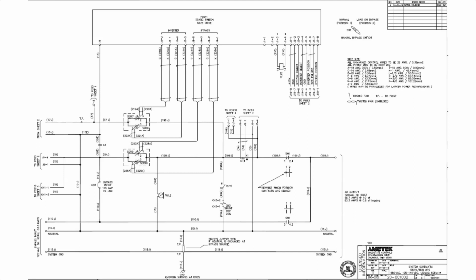So this is the same drawing that we had for the static switch. So you can see once again, here's our inverter static switch, and here's our bypass static switch. But you can see here we have switch 1, and we have two contacts for a manual bypass switch. And when I say a manual bypass switch, that refers to a bypass switch that is actually internal to the UPS. It's on the front of the UPS panel. So it's part of the UPS itself.